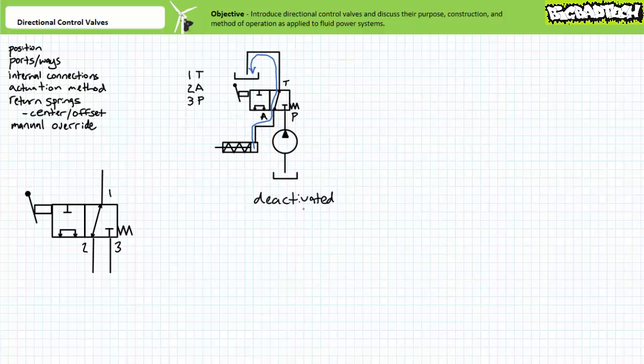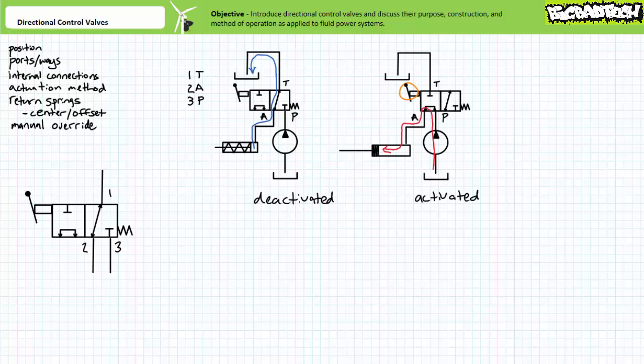Two-position, three-way directional control valves are commonly used to control the actuation direction of single-acting cylinders. Consider a configuration making use of port one as the tank port, port two as the actuator port for a spring-retracted, hydraulically extended single-acting cylinder, and port three as the pressure port. The spring-offset deactivated position blocks the pressure port while the actuator port is drained to tank, allowing the spring force to retract the rod. When the valve is actuated into the second position, pressurized flow is routed to the single-acting cylinder and the cylinder extends. When an operator releases the manual lever, the return spring offsets the valve so the spring force retracts the cylinder.